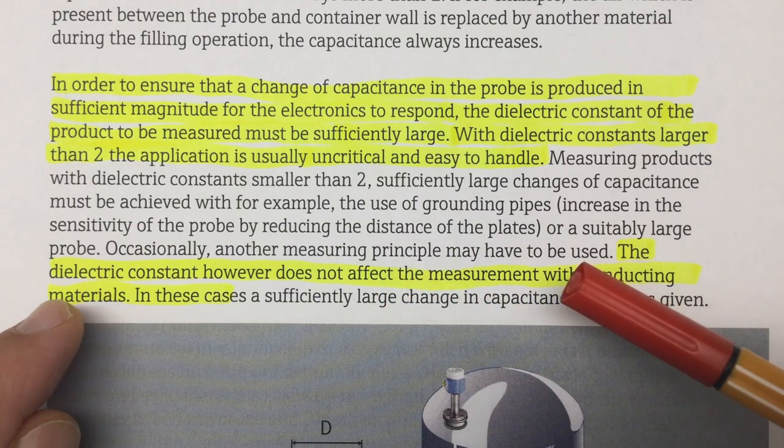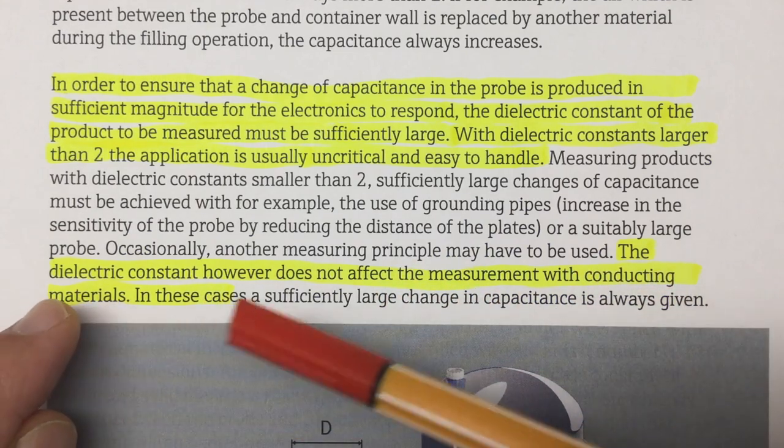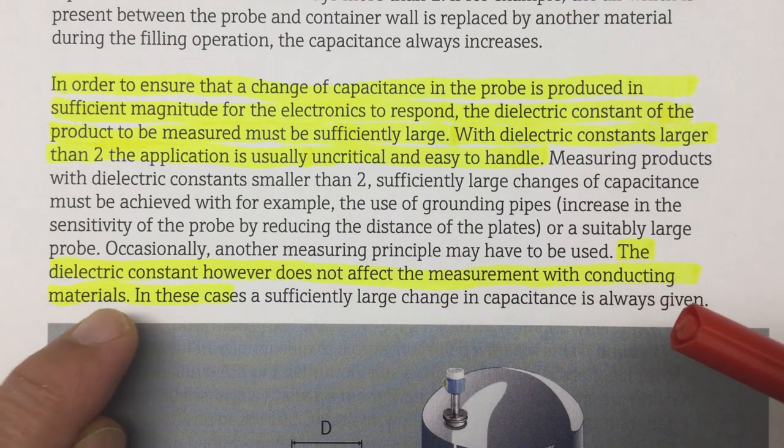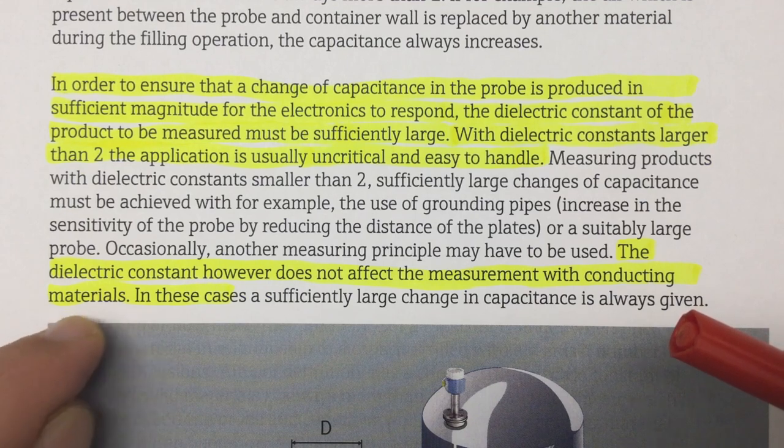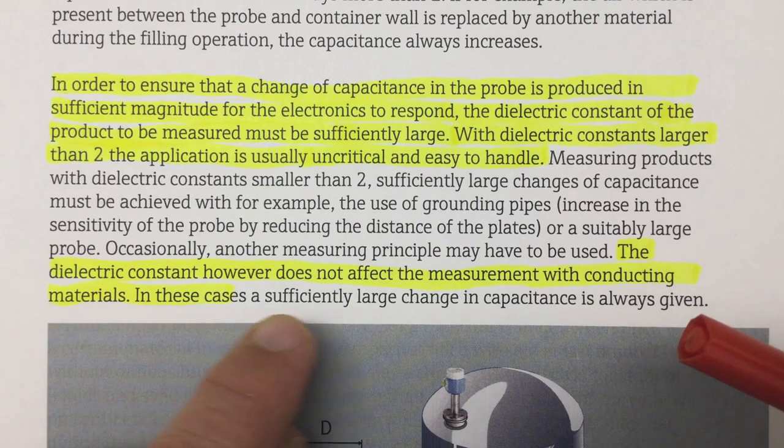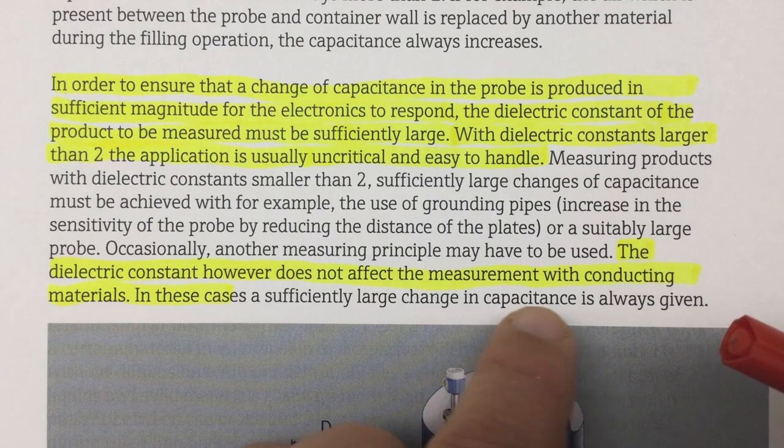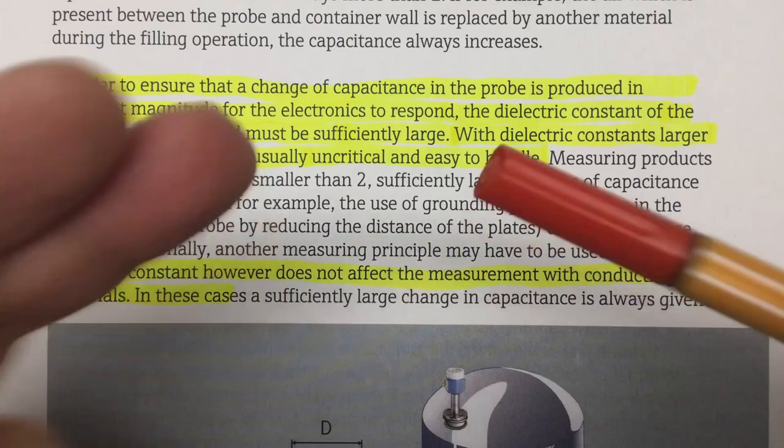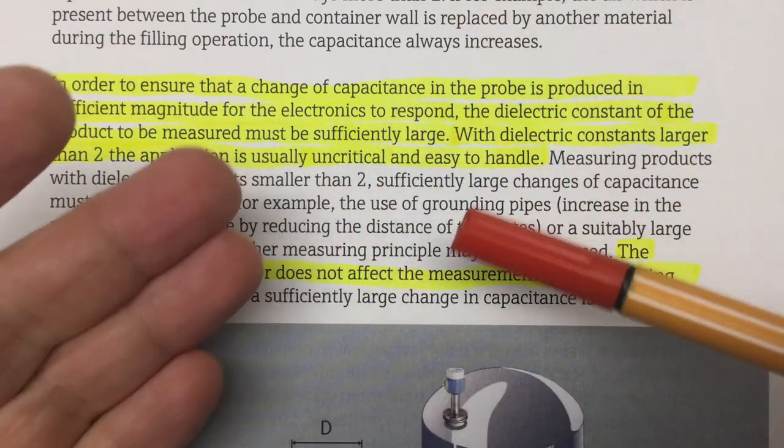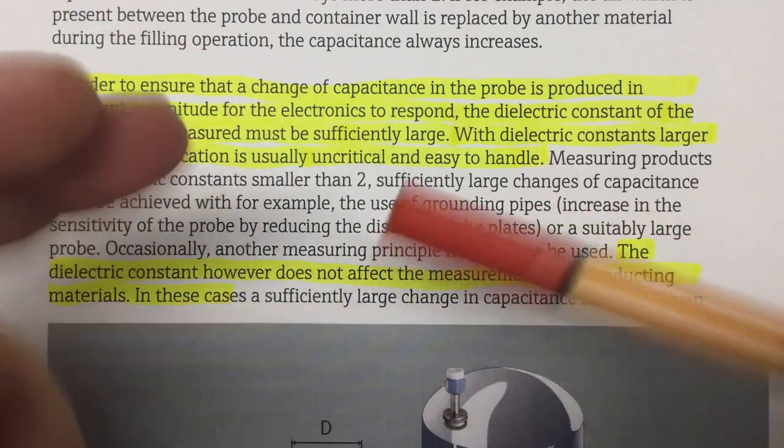So we are talking here about the dielectric constant of our liquid and how it influences the measurement. And it needs to be sufficiently large, larger than air. And they say for their sensors, it's 2 is the limit. But then further down, there's a single sentence. The dielectric constant, however, does not affect the measurement with conducting materials, that is fluids. In this case, a sufficiently large change in capacitance is always given. And we saw with water, saline, alcohol, we always get, because it's a metal sheath analog, you always get a large increase in capacitance.